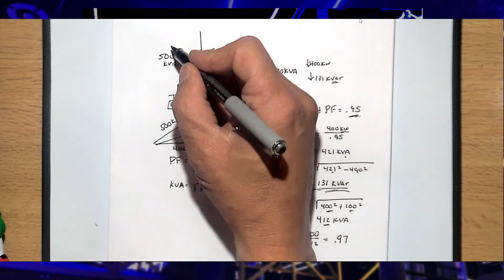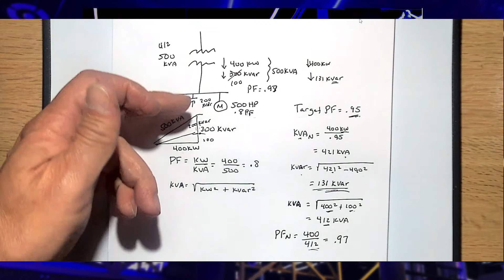And so that leaves me with the capability of adding more load, or as you said, at some point you could even reduce the size of that transformer if you got down small enough. For example, you wouldn't typically take a transformer out and put a smaller one in, but the point is, you wouldn't have to put a bigger one in to add more load.